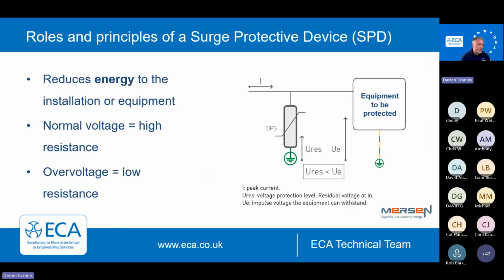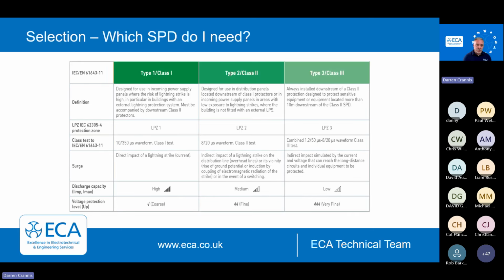How do surge protection devices work? Very, very easy. They literally just go conductive. They must always sit before the equipment they're protecting, otherwise they're useless. And the whole idea is that when an overvoltage occurs, they go to negligible impedance and conduct to ground. Very, very simple devices. As we spoke about earlier in this presentation, Type 1, Class 1 are your robust ones. They're much more expensive. They're much more robust in their construction because they have higher faults and higher voltages and currents that they need to put down to ground.